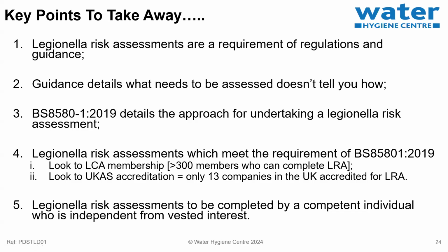So if there is an organisation doing a risk assessment for multiple buildings across a portfolio, and the recommendation might be to clean and disinfect the tank, okay, that's a valid recommendation. But from a hierarchy of controls, what could we do that would potentially reduce the risk even further? We could look at removing the tank. Do we actually need the tank to be there? Can the tank be removed? It could go directly onto mains fed.